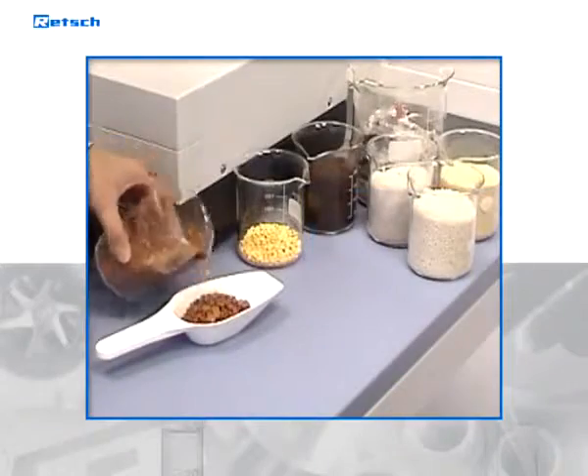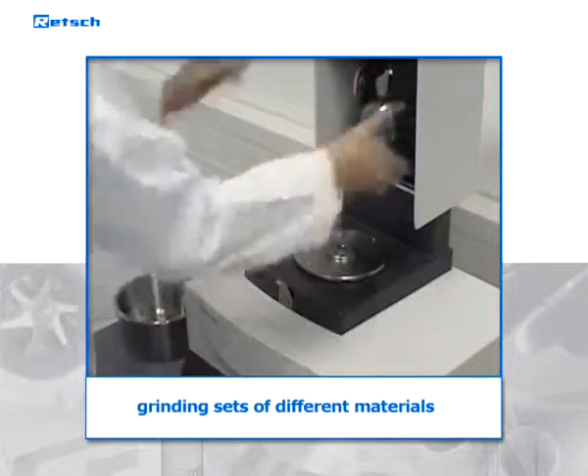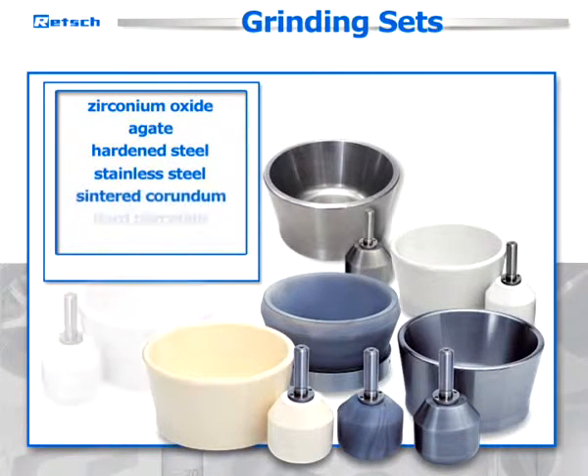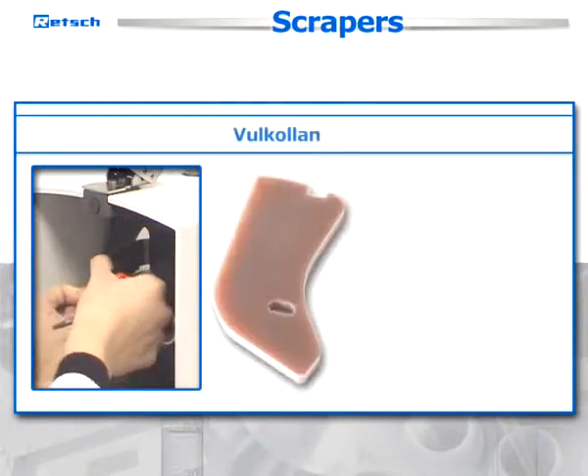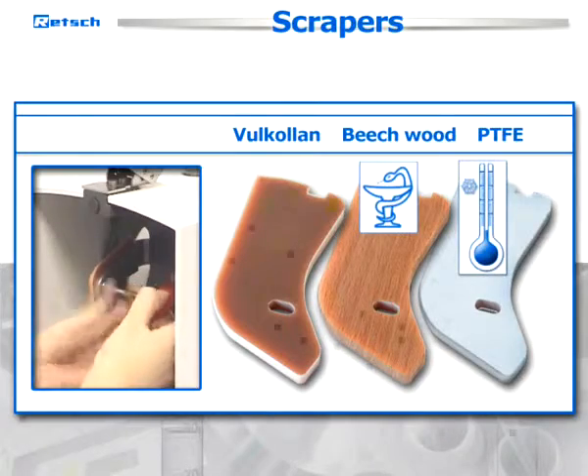The RM200 can process batch sizes from 10 to 190 milliliters. Grinding sets of different materials are available and ensure neutral-to-analysis grinding procedures and customized use. Available materials include zirconium oxide, agate, hardened steel, stainless steel, sintered corundum, hard porcelain, and tungsten carbide. Scrapers are made from Vulkollan or Beechwood for pharmaceutical applications, or PTFE for cryogenic grinding processes.